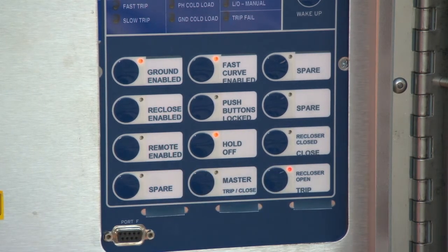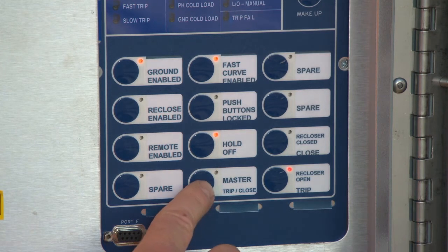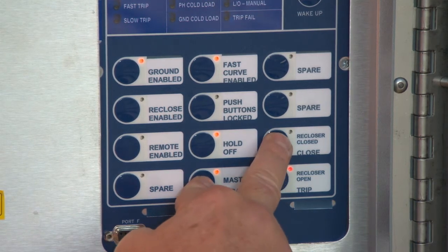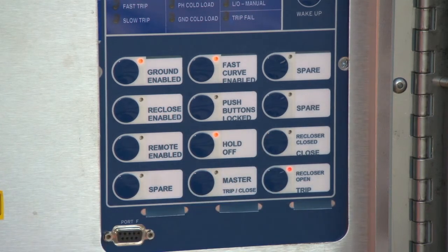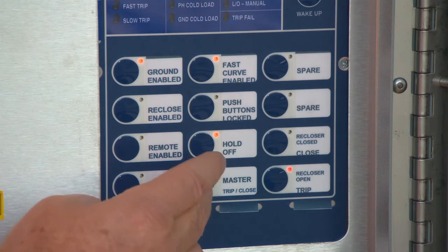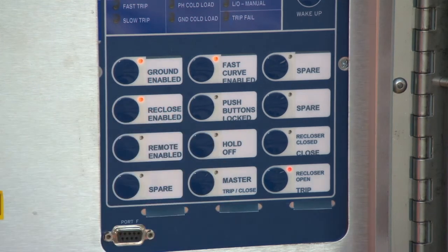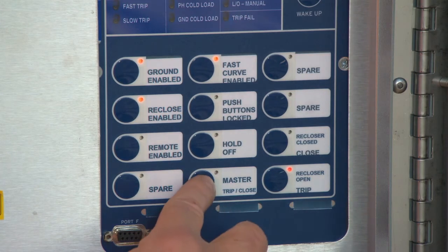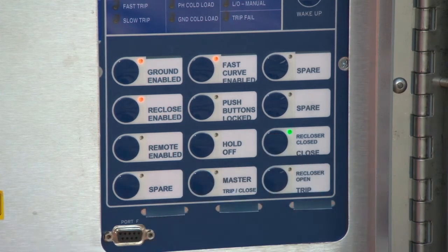When the recloser has tripped out under a hold-off condition, the recloser cannot be closed until the hold-off has been removed. You will notice that after pushing the master and recloser closed buttons together, the recloser does not close. To turn off the hold-off, press the master and hold-off buttons together. Reclose enabled will become active, and you will now be able to close the recloser.